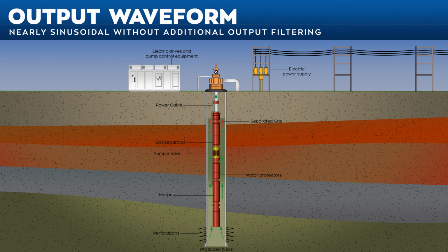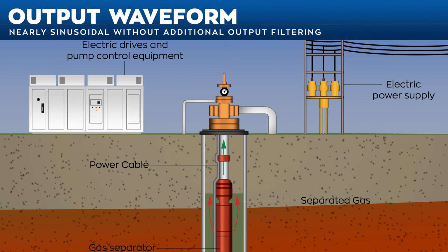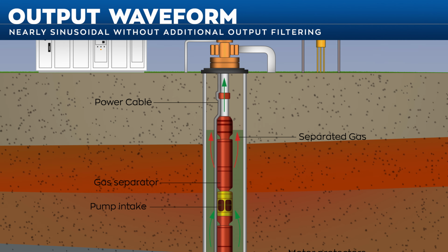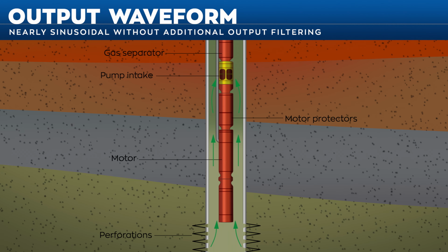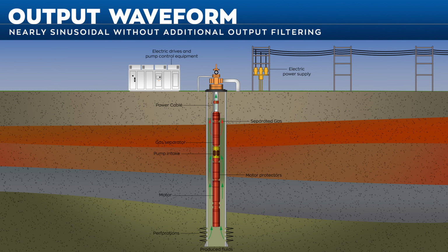This is especially important in applications like electric submersible pumps, where it is common to have a very long motor conductor between the drive on the surface and the downhole motor.